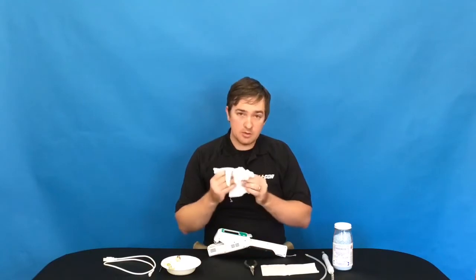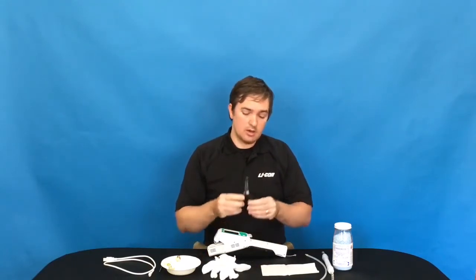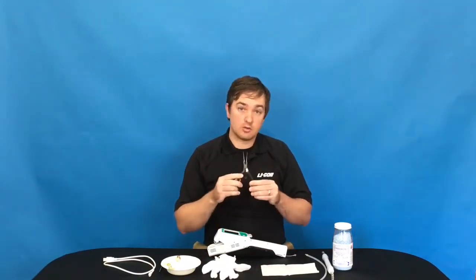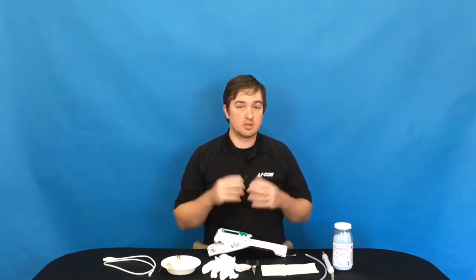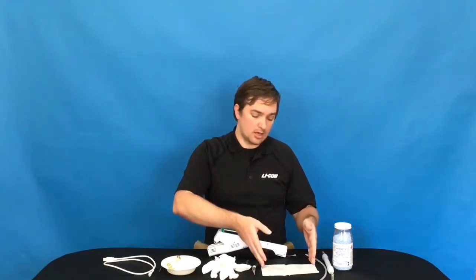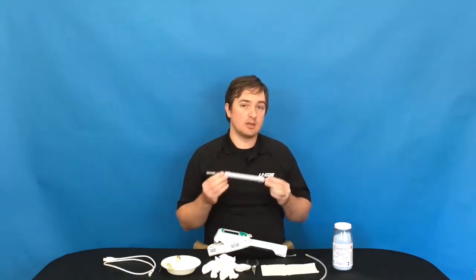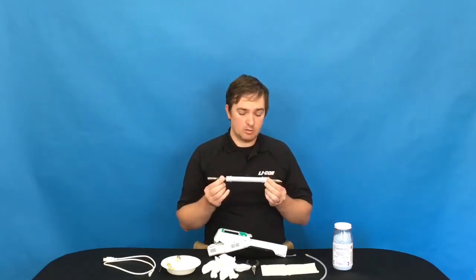We'd also recommend using gloves and or needle nose pliers or tweezers or forceps to remove the buffer beads. There are small beads inside the instrument that need to be removed so that they don't interfere with the calibration. Those beads should be placed on a Kim wipe or a sterile glass jar so that they are not going to get dirty.